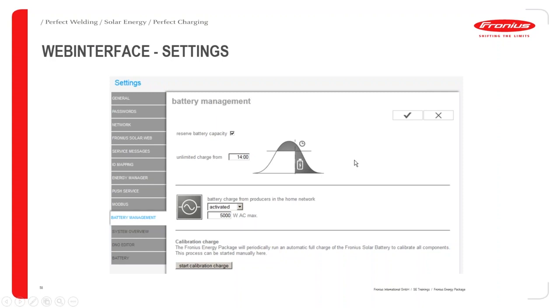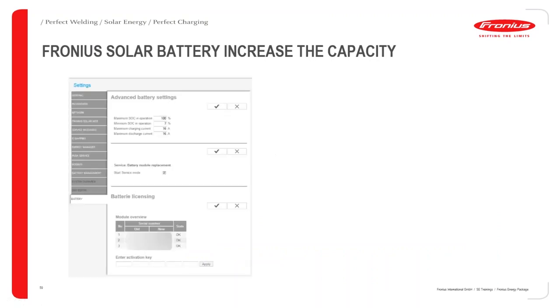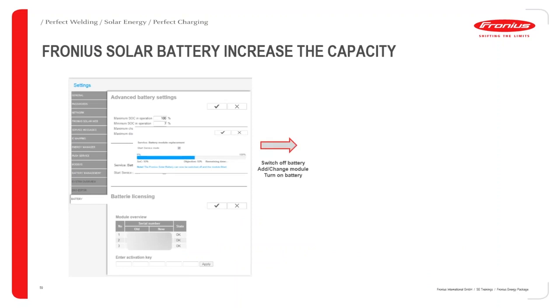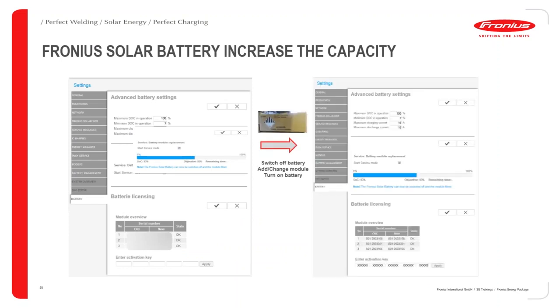So just going back to the settings there again as well. So battery management, here you can actually physically manually start the calibration charge if you wanted to. Then you've got another spot here if you want to change the battery charge from other producers in the home. This unlimited charging is more for Germany, so reserving capacity, the unlimited charge. They've got a rule in Germany that you have a 60% export rule if you have batteries. So this is to organise that, with your 60% export limitation rule, you're making the most of the battery there.